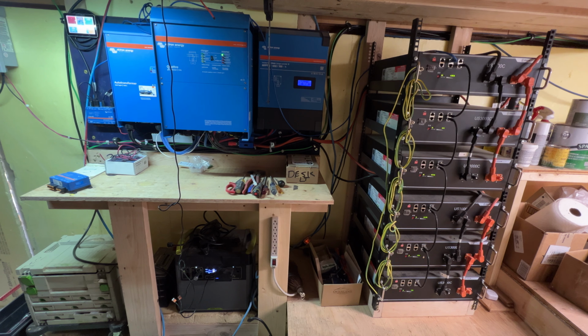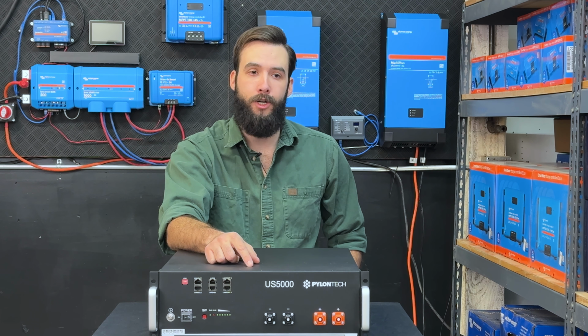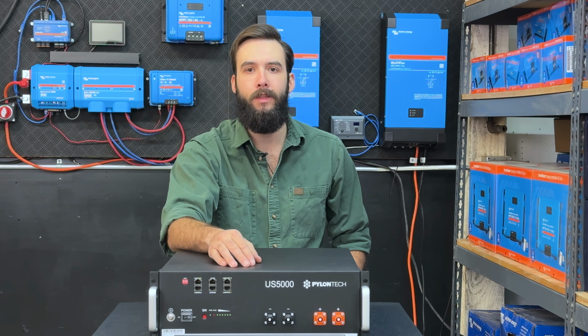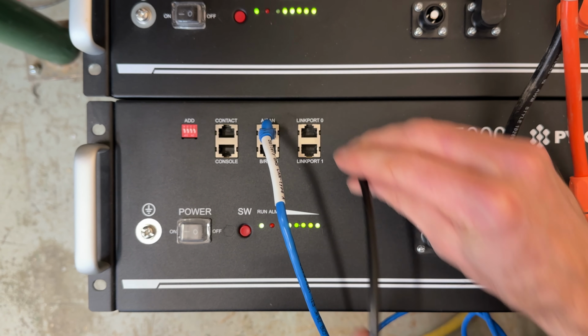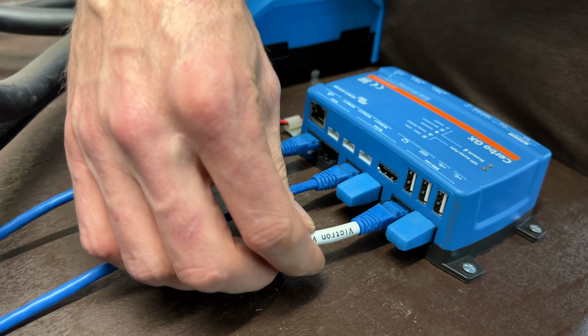Pylontech actually takes a step further than that and manages the battery, particularly a string of batteries if you're using multiples connected in communication, to optimize performance. The master battery will actually communicate a lot of what's going on in the subsequent batteries up to your inverter or your connected system and allow optimization of charging, discharging, allow individual batteries to go online or offline based on the conditions, such as, say, temperature, without interrupting total operation. The BMS then makes all of this information available via CAN bus or RS485 for modern closed-loop communications with a variety of the best inverters available on the market.